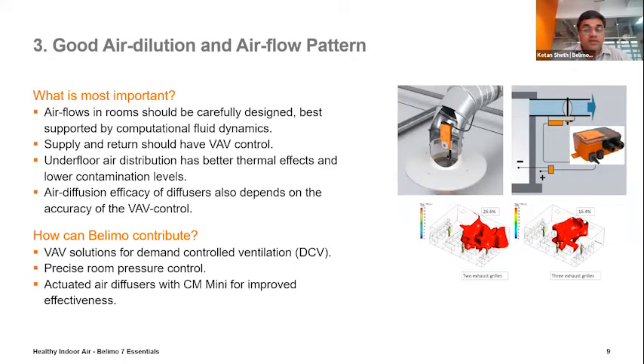The third essential is the good air dilution and the airflow patterns. Airflow in each room should be carefully designed, because we have seen that most of the time there is a lack of CFM or there is more of a CFM. So that also needs to be properly controlled. And for that we propose supply and return VAV control for the closed rooms.